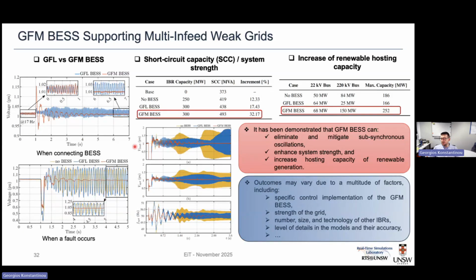We do get some additional benefits when we look at traditional definitions of system strength. We're looking at higher short circuit capacity and an increase in the fault current if we were to do traditional fault current calculations. And you can see here an increase of around 32% in the short circuit current capacity we can get at a particular location. That's short circuit capacity, so fault level at this particular location.